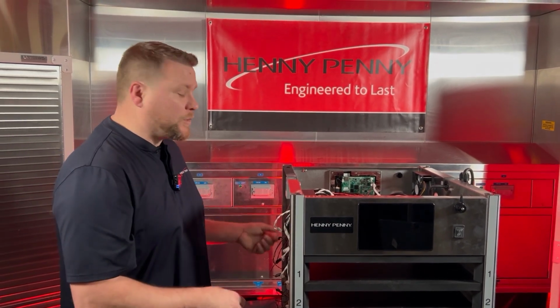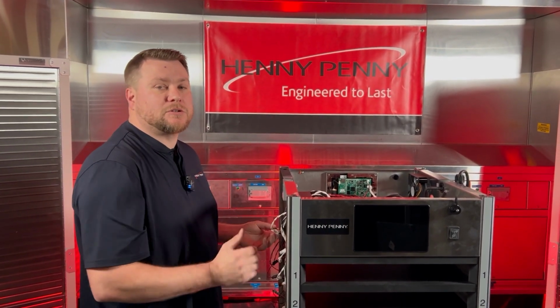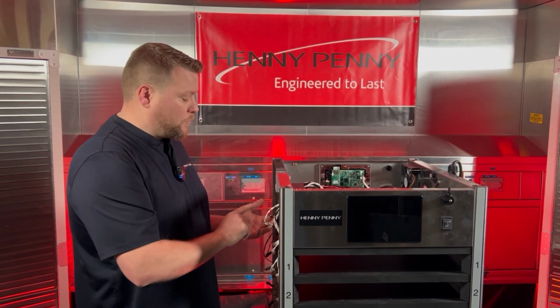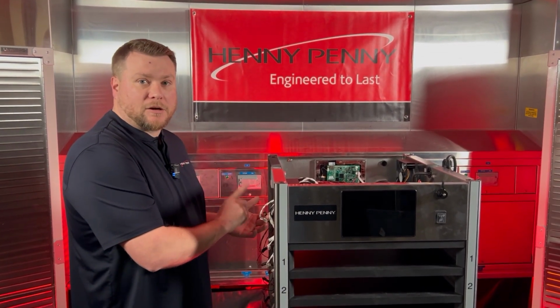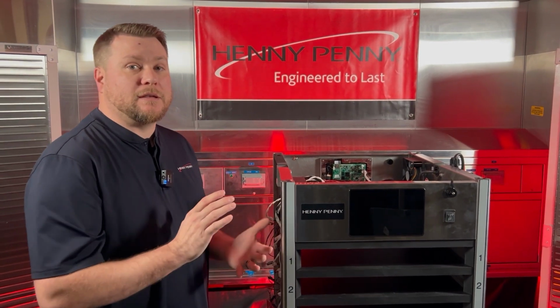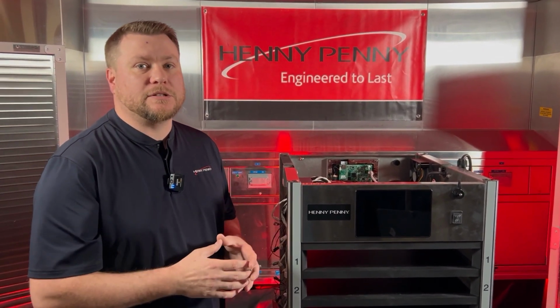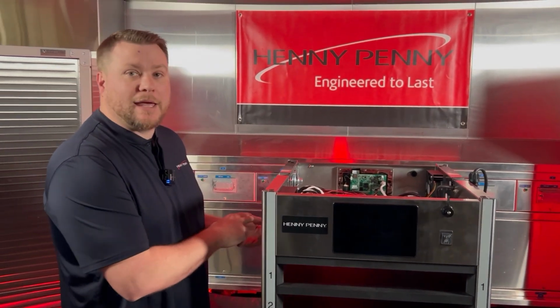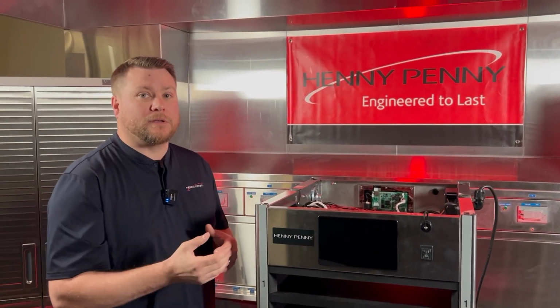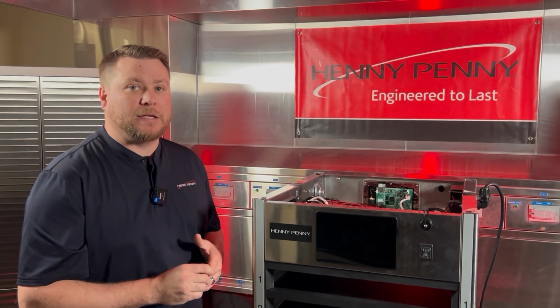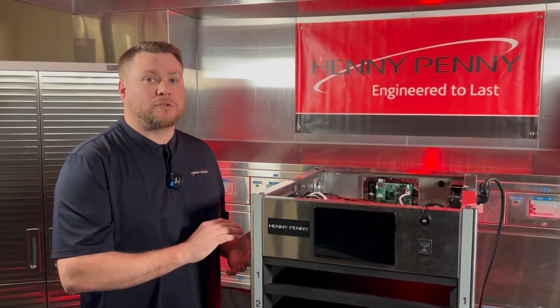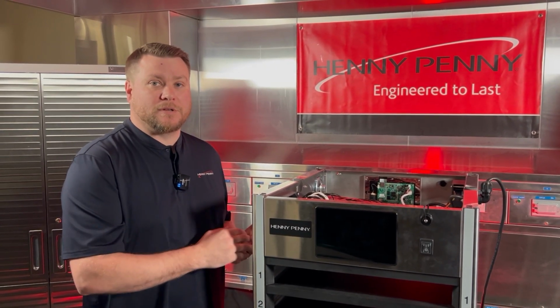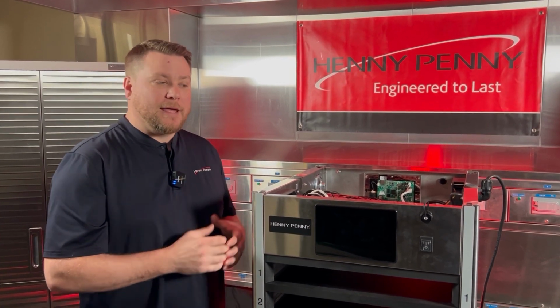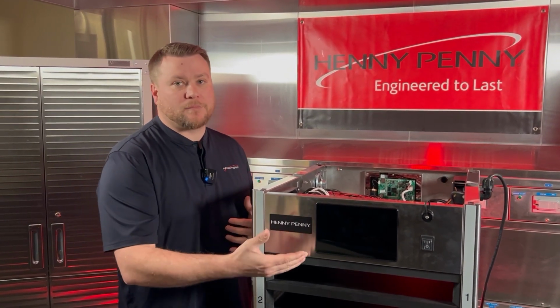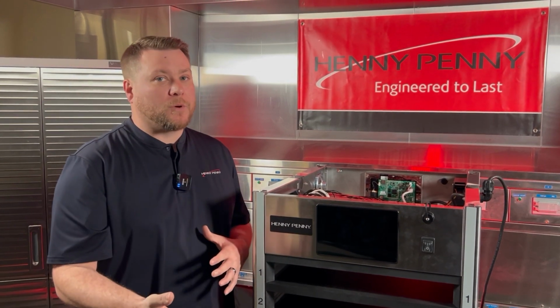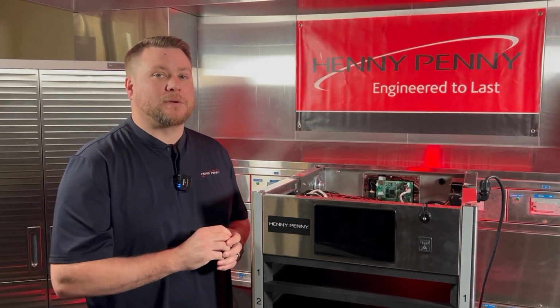The other thing is we could check our temperature probe just to make sure that it's within calibration, and we could unplug it here and check our resistance. Remember, we're using the 1000 ohms at 32 degrees Fahrenheit scale. So we could go ahead and get our readout of the temperature probe of what it's saying on the screen, and then we could compare that to our multimeter and what it's giving us on resistance and compare that to the chart. And that would let us know if we have a temp probe or a heater issue. Either way, it's likely going to be a heater replacement.